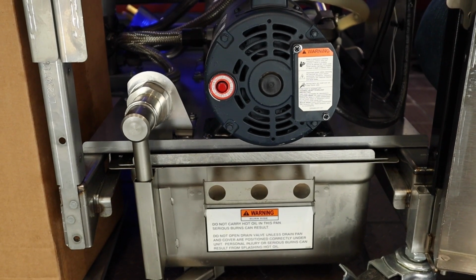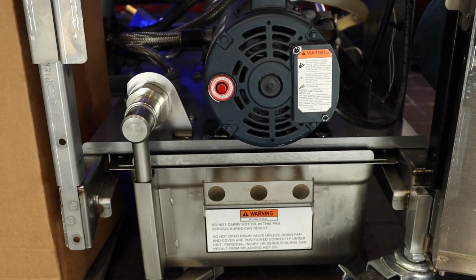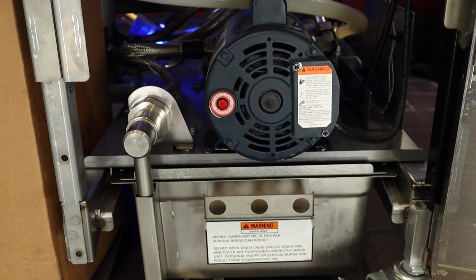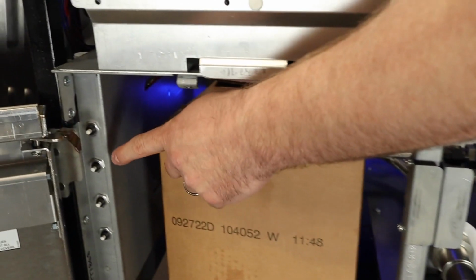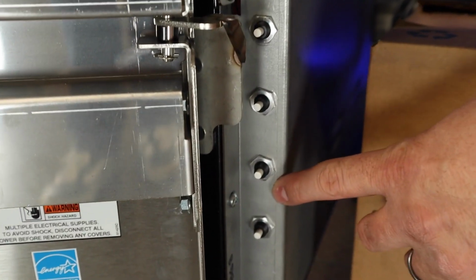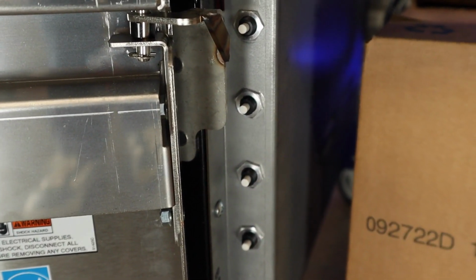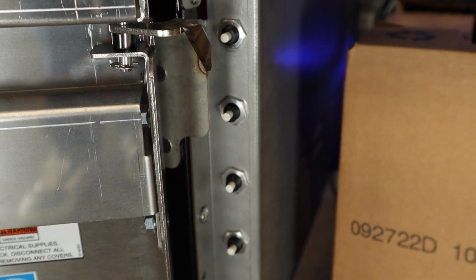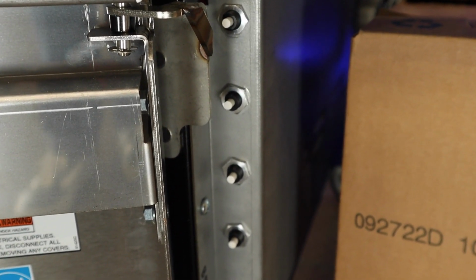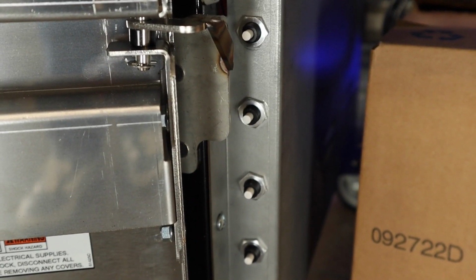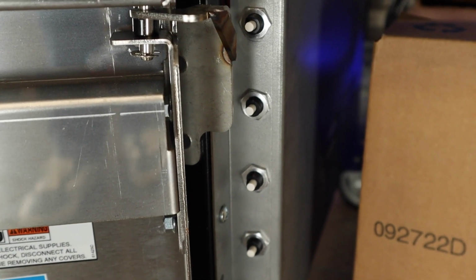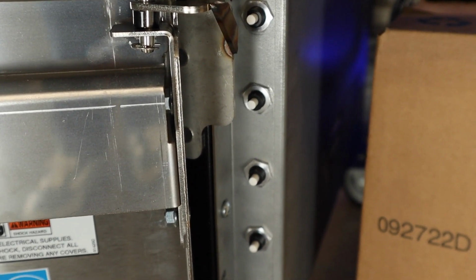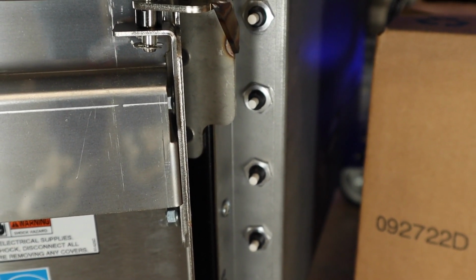If it's not the thermal overload, then we can make sure that one of the circuit breakers over here on the left-hand side is not tripped. It will be one of the bottom two circuit breakers. So if we push those in and they click, that means that they were tripped. If that was the case and one of them was tripped, then that could mean that we have an issue with the filter motor if it continues to happen again.